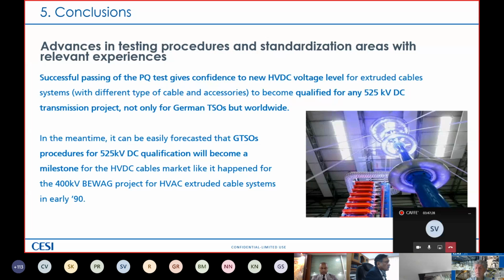Of course, someone may say that there is a very low field experience coming in the HVDC sector, even for lower voltage level. For example, interconnections of 320 kV are quite a few around the world. But the specific request of the German TSOs to have this higher voltage level was related to the fact that they need to transfer a lot of power from the Baltic Sea, from the North Sea, to the southern part of Germany, where the main industrial areas are. So we had a big jump, but a few years ago, we moved from this 320 with quite a few information gained from the field to this 525.